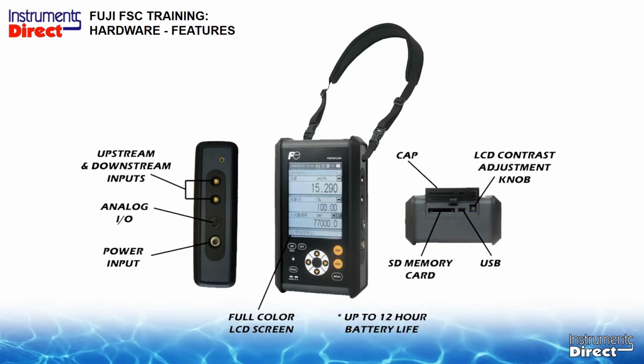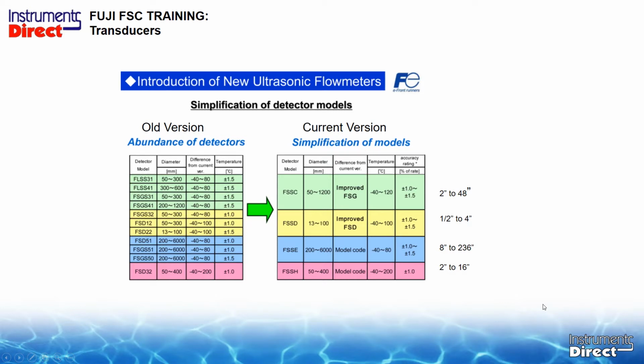Alrighty, here we go. This is the handheld portable Fuji ultrasonic flow meter, the Portaflow C, model FSC. This is the device that, of course, would indicate what your flows are, log your data, and so on. This device will then get hooked up through signal cables to the clamp-on transducers. Over the years, Fuji likes to continually upgrade and change the transducer part numbers. The current transducer versions are in the chart on the right. You can still use the old transducers on the left, but if you upgrade to the new FSSC 1 megahertz transducer, you will need to update your firmware, which is not a big deal. We can help you do that, or you can do that yourself. So basically, this is the new set of transducers, or current set of transducers for the Fuji Portaflow C.